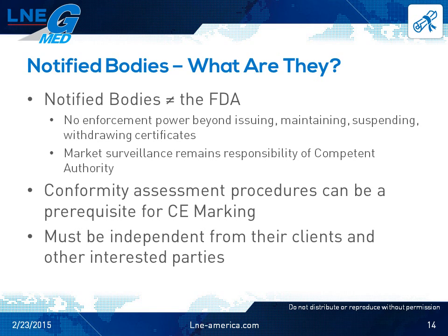Now, the last note on this slide is that notified bodies must be independent from their clients and other interested parties. It's true that notified bodies are commercial entities, and that medical device manufacturers have to pay for their services. However, a notified body can't be owned by a medical device manufacturer or be otherwise economically tied, to make sure that the notified body maintains its independence.